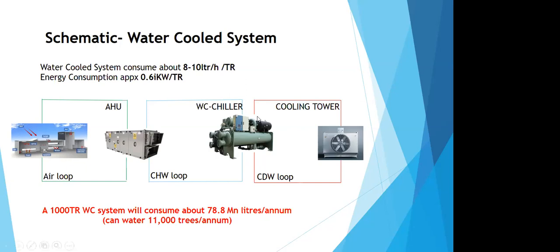We have three loops. We have a condenser water loop, which is catering to the cooling tower. Then we have the chilled water loop, where the chiller is supplying chilled water to the air handling unit. And then we have the chilled air loop, where the air handler supplies the cold air to the heat load. Now, in such a system, the water consumption of the cooling tower comes to around 8 to 10 liters per hour per ton of refrigeration.